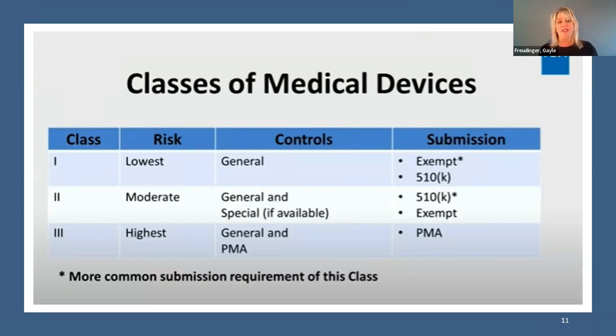Class one devices are low risk devices. They require general regulatory controls. Most devices in this class are exempt from any pre-market approval from the FDA. So you can go ahead and put your product out on the market, but sometimes a 510(k) submission is required if there's some risk associated with it. Examples include Band-Aids or bandages, handheld surgical instruments, and non-electric wheelchairs, just your basic wheelchair.